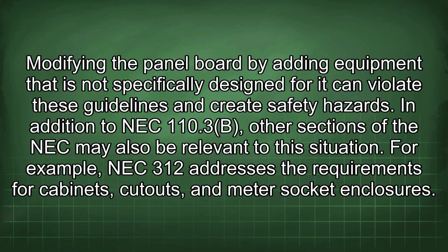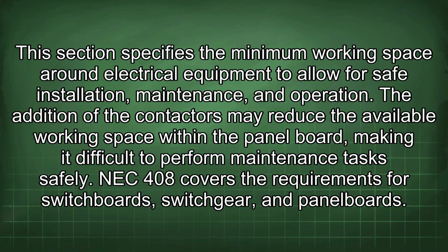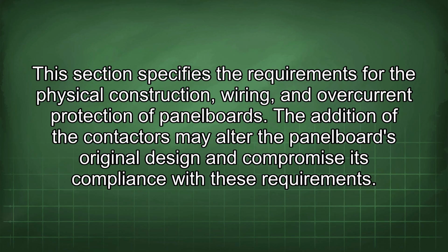In addition to NEC 110.3(B), other sections of the NEC may also be relevant to this situation. For example, NEC 312 addresses the requirements for cabinets, cutouts, and meter socket enclosures. This section specifies the minimum working space around electrical equipment to allow for safe installation, maintenance, and operation. The addition of the contactors may reduce the available working space within the panel board, making it difficult to perform maintenance tasks safely. NEC 408 covers the requirements for switchboards, switchgear, and panel boards. This section specifies the requirements for the physical construction, wiring, and overcurrent protection of panel boards. The addition of the contactors may alter the panel board's original design and compromise its compliance with these requirements.